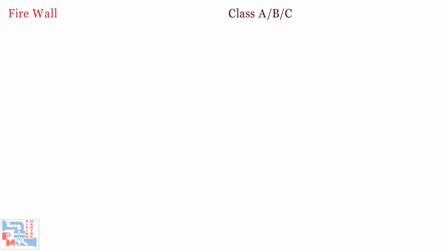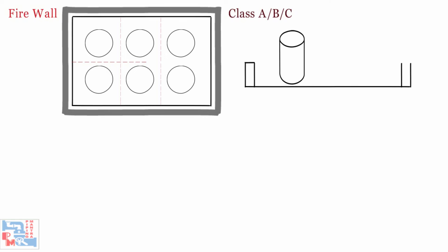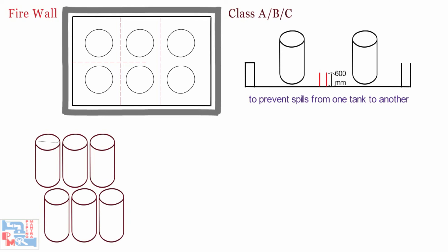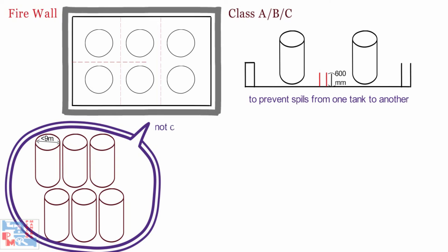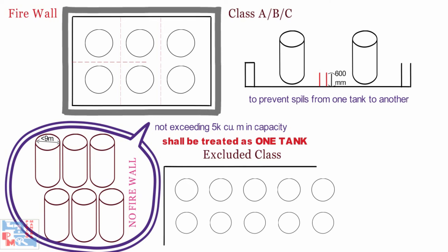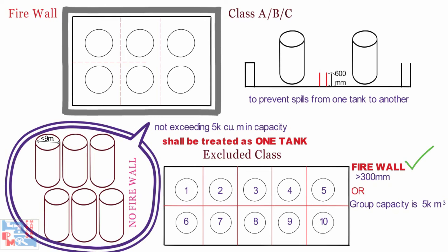Now comes firewalls. For Class A, B, and C petroleum, in a dike enclosure where more than one tank is located, firewalls of minimum height 600 mm shall be provided to prevent spills from one tank endangering any other tank in the same enclosure. A group of small tanks, each not exceeding 9 meters in diameter and in total not exceeding 5,000 cubic meters in capacity, shall be treated as one tank for firewall provision. For excluded petroleum product storage, firewalls shall be provided by limiting the number of tanks to 10 or the capacity of the group to 5,000 cubic meters, whichever is lower. Firewall height should not be less than 300 mm.